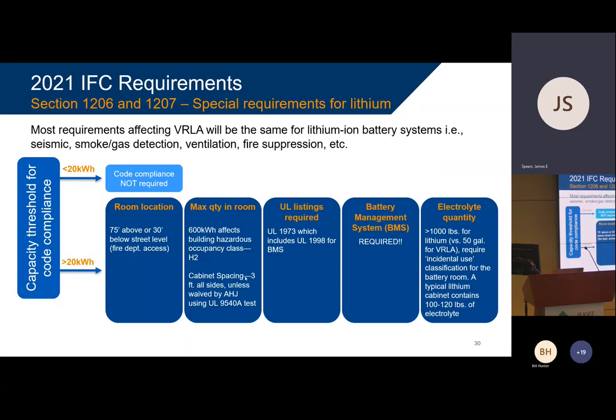Notice that the code says cabinet spacing 3 feet on all sides, front, back, left, right, unless it's waived by the authority having jurisdiction using the 9540A test. Almost no users of the tens of thousands that we have are doing this because they have that UL 9540A test that says flames don't propagate. Got to have UL 1973. You have to have a battery management system. If someone tries to sell you a box of lithium batteries with no BMS, you should run and run now because you'll be running eventually. Got to have battery management system per the fire code.